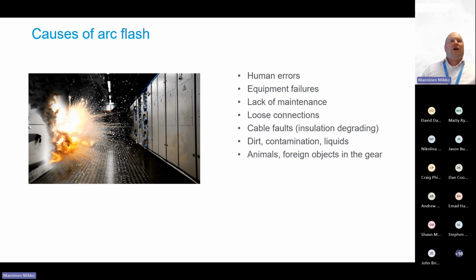For example, arc flash. What happened in the coal-fired plant, all the coppers and all the circuit breakers were full of coal dust, and coal dust is explosive. When you do switching, you can count 1 + 1 and estimate what will happen, because it will happen. Animals, foreign objects in the gear, like a tool, and then rats.